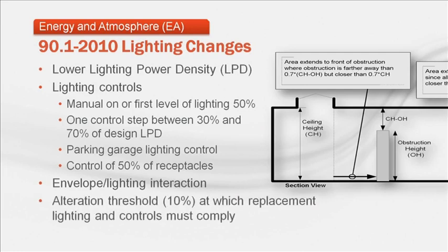Now, a pretty major change was that once 10% of the luminaires are replaced during alteration, lighting controls must also be upgraded. There were a significant number of mechanical changes too. We'll touch on a few of the major ones.